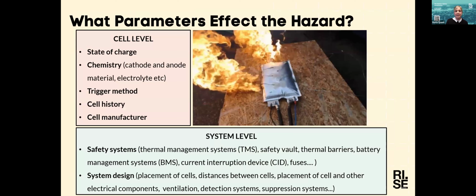Before I hand over to Franz, I want to discuss the parameters that can affect the hazards, depending on what level we're talking about: cell level and system level. At cell level, state of charge, chemistry, trigger method, cell history, and cell manufacturer influence the hazard. At system level, it's safety systems such as thermal management system, safety vault, thermal barriers, battery management system, current interruption devices, fuses, and so on, as well as design choices like cell placement, distance between cells, placement of other electrical components, and safety systems such as ventilation, detection, and suppression systems.